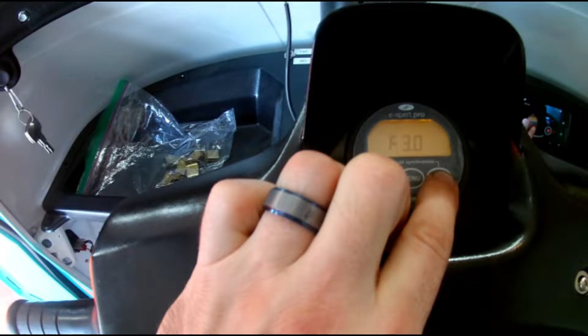Section 3.0 through 3.5 are all about critical low battery voltage. You see, just because the battery monitor is showing 0% state of charge does not mean the batteries are at 0 volts. Rather, the battery pack operates in a safe range of 45 volts to 51 volts, with 45 volts being like 0% stated charge and 51 volts being like 100% stated charge.